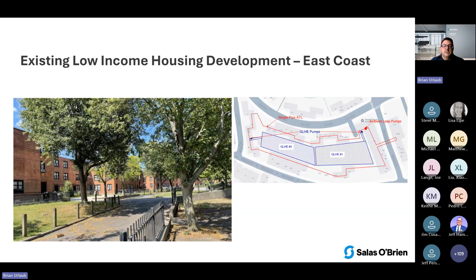A couple of interesting things I want to point out. Again, space is a big concern. This is going to have to be an angle drilled or incline drilled bore field system because there's no space, and there's a ton of utilities that run through here. Thankfully they have pretty open basements, so we can run in and out of the building's basements for the ambient loop. We do have to cross a street to get to the building on the right. The ambient loop pumps are going to be in the old steam boiler room.